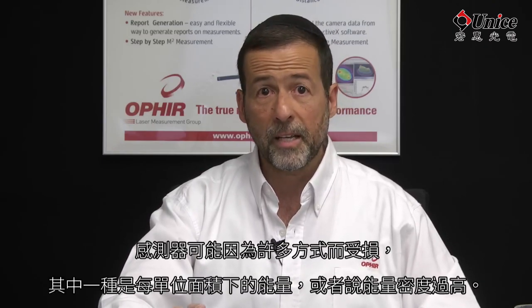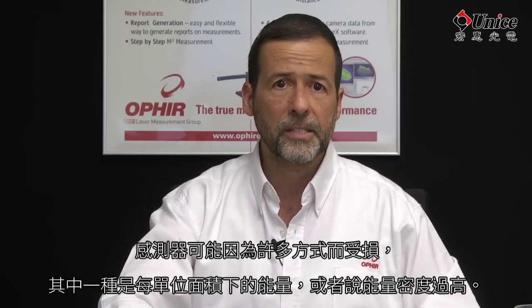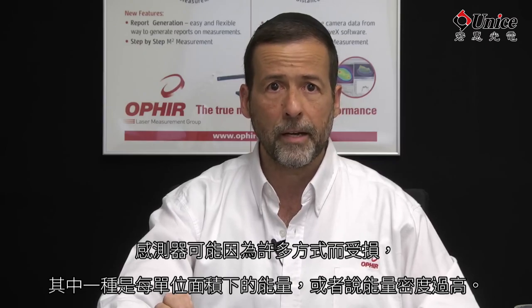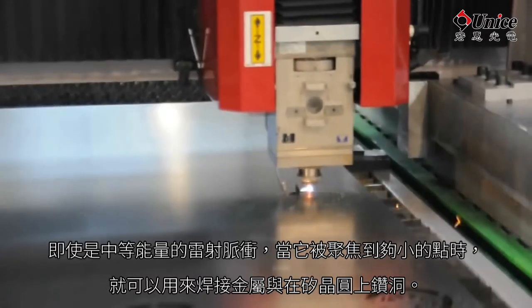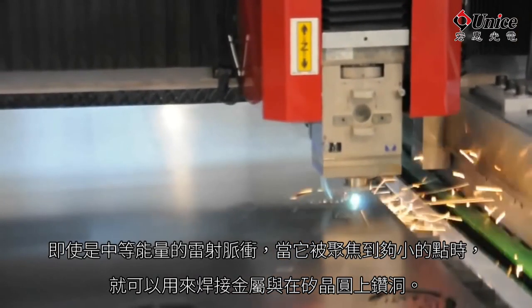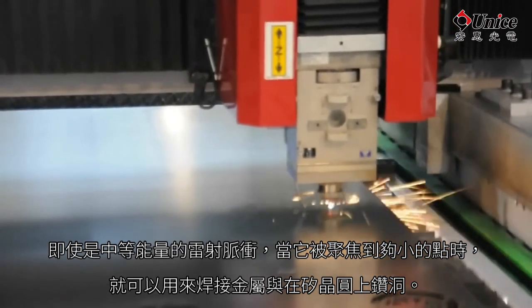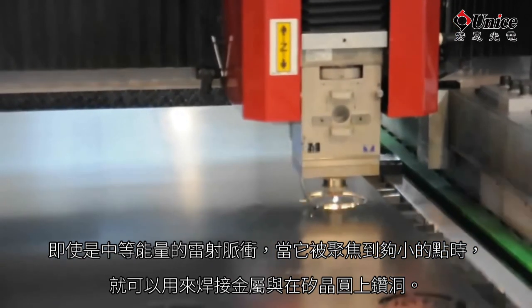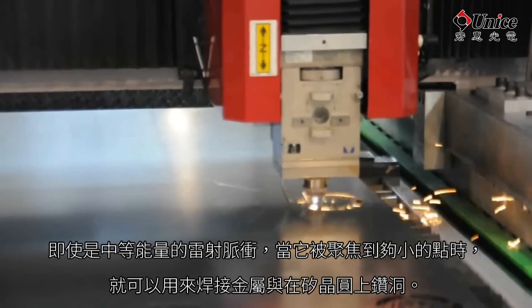Why, you may ask, are there these two different terms for describing laser power? In many cases, it has to do with damage threshold, the ability of a sensor to survive the experience of measuring a beam that it's placed in front of. Sensors can be damaged in many ways, and one of them is too much energy per unit area, or energy density. Laser pulses of even moderate energy can, when focused down to a small enough spot, be used for welding metal and drilling holes in silicon wafers.